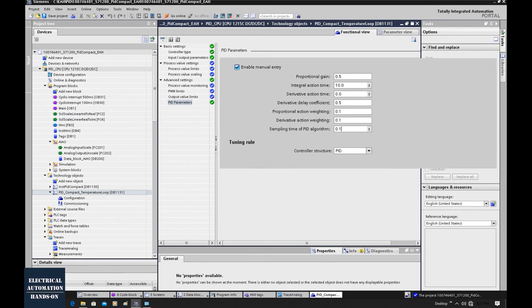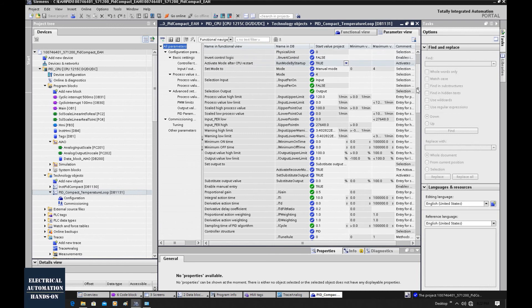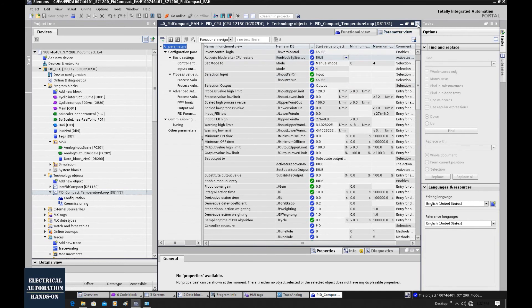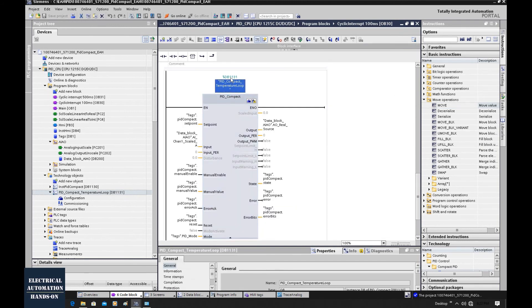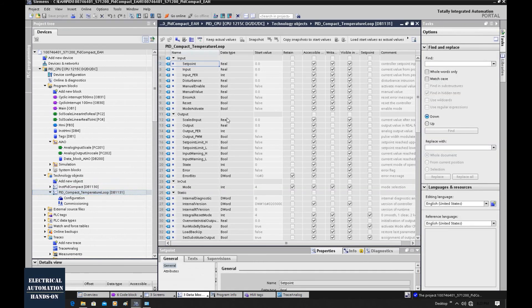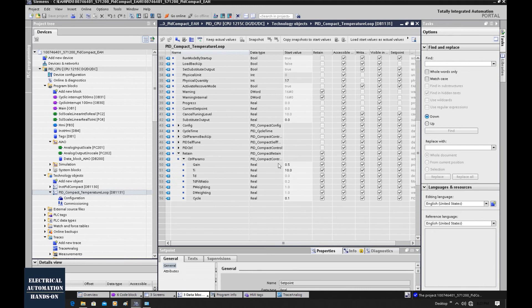Those are the initial settings for this PID loop. To check out the detailed parameters of this PID controller, we can also go to the parameter view — all those parameters are shown there. There is another way: if we close the parameter view, the instance DB of this PID control loop is DB1131. We can right-click and select Open DB Editor. This allows us to use the traditional way to look at all detailed parameters, especially the PID parameters including the actual gain, TI, and TD. If we want to write PID parameters directly from the program, we can drag these three tags into the program and write values directly to gain, TI, and TD.